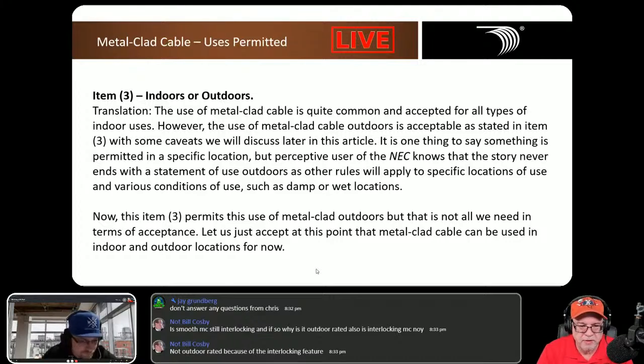Bill asks, is smooth MC still interlocked? No, smooth is a continuous extrusion, so it has a little different rating. For example, normal MC's armor can't be used as an equipment ground, that's just normal MC. Whereas smooth MC's armor can be used as an equipment ground inherently because of how it's extruded over it.